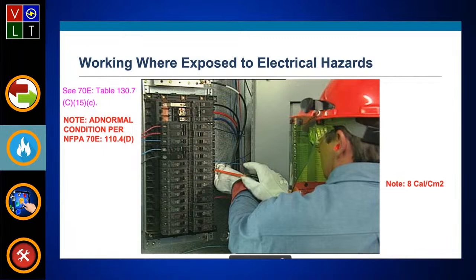So my question was, does it become abnormal operation once the dead front is removed? If he removes that panel board and gains access inside, most requirements say yes, he would need that equipment. But some folks interpret it to say that as long as he just removes the panel cover, he might not need it on. Everybody I've talked to says you're going to need your equipment on because you're gaining access into it. Now he's doing a job task, tightening a screw, so he could go through the tables—there are three tables we'll see—or calculate it. But as long as the cover's on...